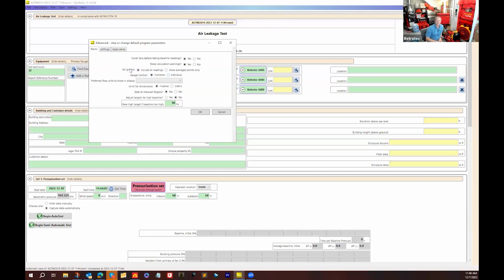So just to add to that real quick, the setup that Sam was just showing with the cabling would be hardware daisy chaining, where you're physically connecting the drives together. So you have one gauge control both fans. This setup window is software daisy chaining or software control. So this is saying that the software is going to try to send either the same speed control signal to all gauges, or it'll tell each gauge to get the pressure individually.